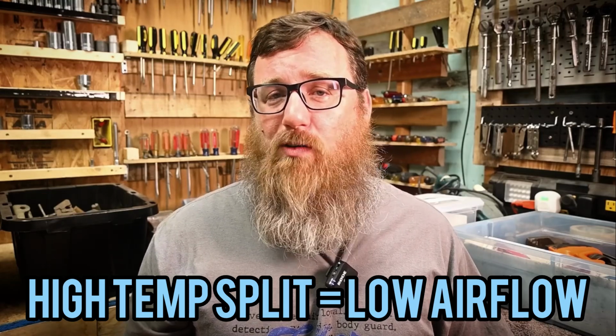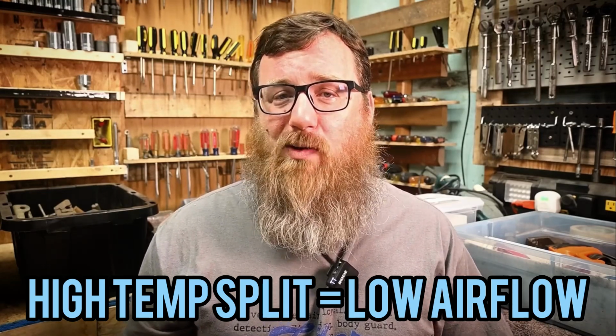If you have a split that's in the low 20s, then you more than likely have low airflow because the air is moving slower across the coil. It's getting colder as it passes through the coil, and that's why you have that wider split. And you can address this by measuring CFM directly with any number of devices, but to get a rough idea, this is an easy way to do that.